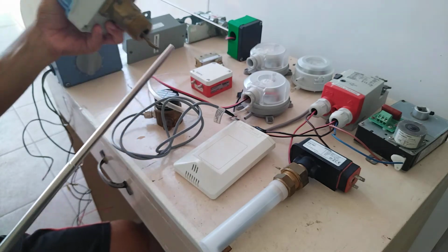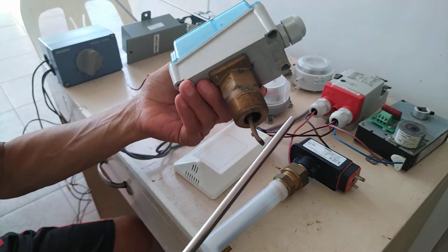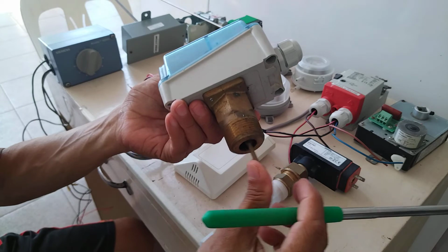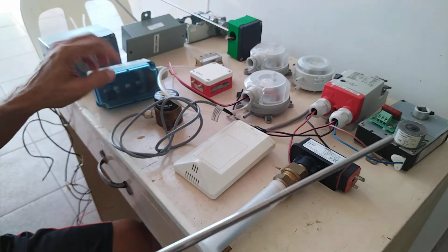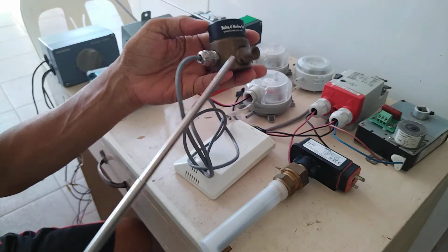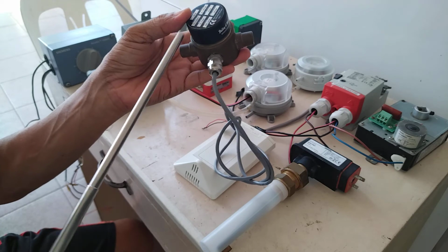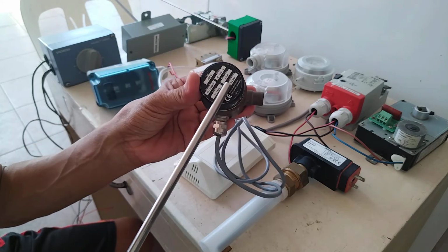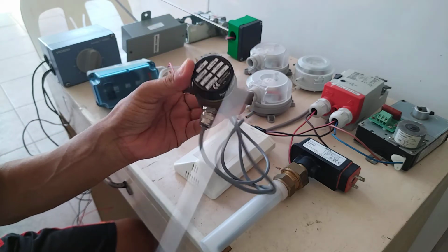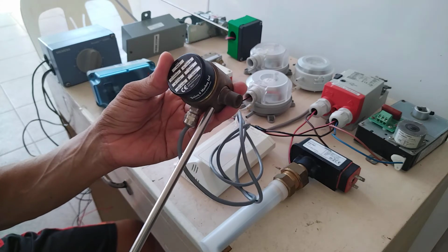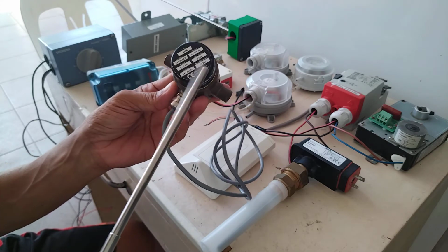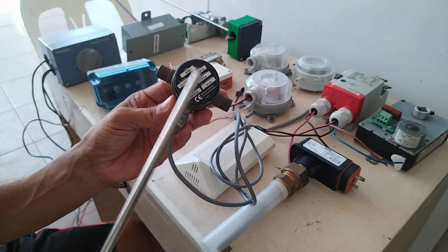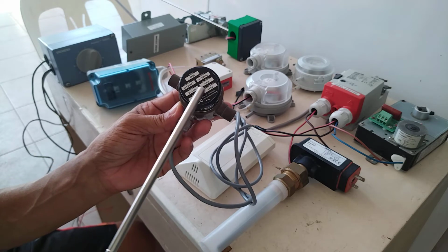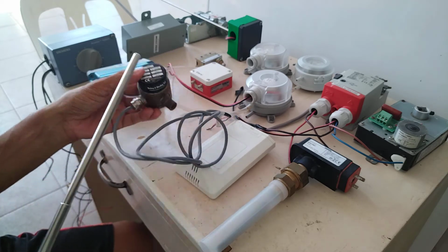Now, what I have here is another water flow switch, okay? To sense the water flow. Then this one is a water differential pressure sensor, okay? Now, this one can be used for sensing the differential pressure, okay? Then we can also use this one for sensing the level of the water inside the tank, the water tank, okay?